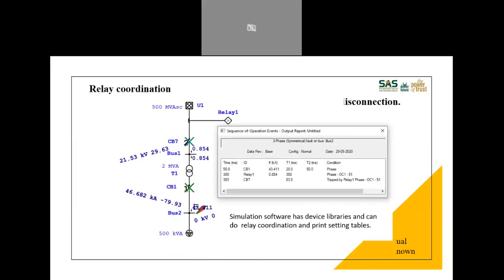See, these softwares can probably offer you such precise tables for setting of your relays. Now, this particular table talks about CB1, Relay 1, CB7, because I have not selected this component, but if I select them, so many columns are added in between where it says make, model, and which curve you have used and what type of setting you have done, which setting is set at what. All those reports can be generated, and coordination also can be done very easily.